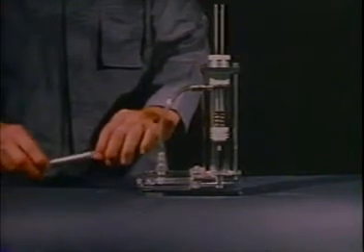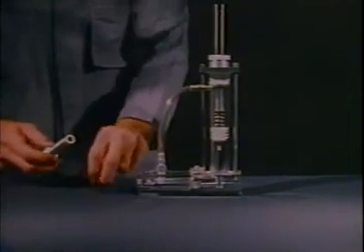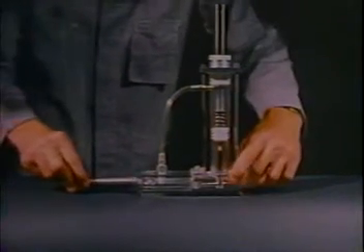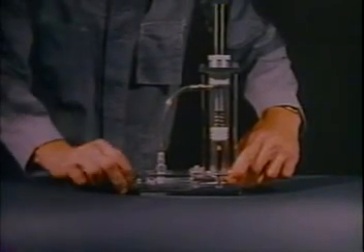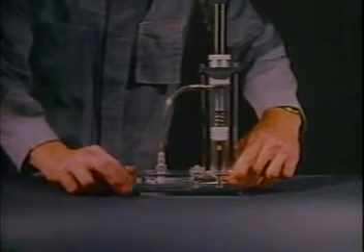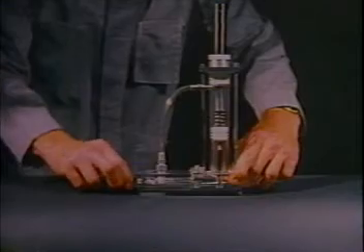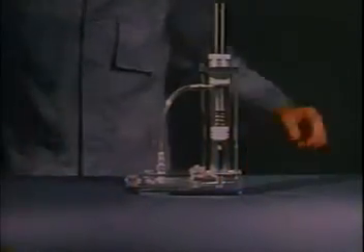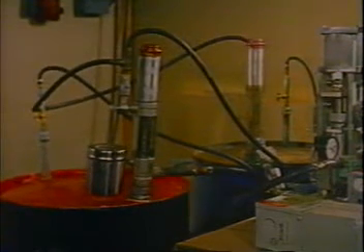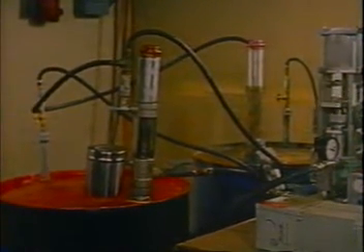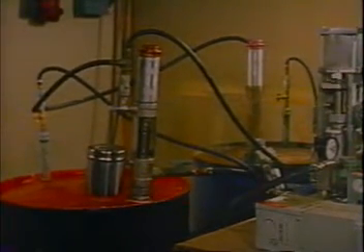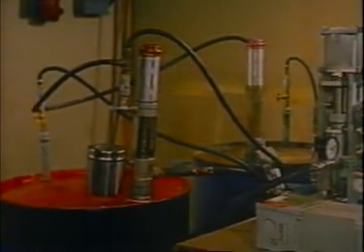A screen placed at the pump inlet before the ball valves filters solid particles which would lodge in the ball valve seats and prevent 100% liquid sealing. The mechanical makeup of these piston pumps makes it virtually impossible for proportion to drift as long as they are completely filled with liquid on each fill stroke from a material supply system such as these transfer pumps.